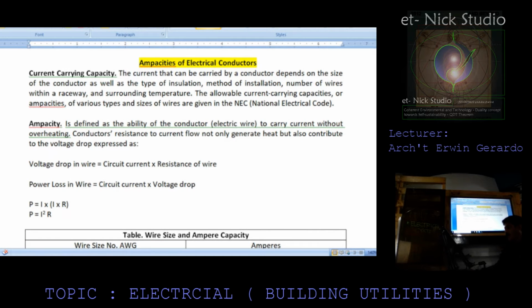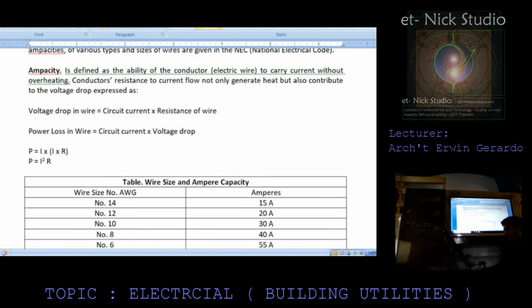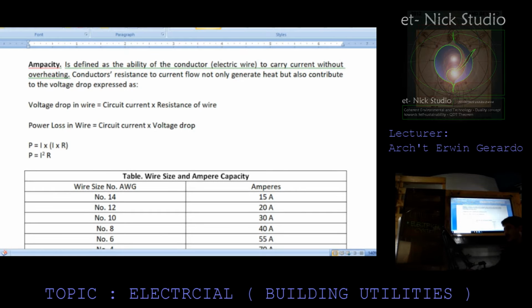Ampacities of electrical conductors. Current carrying capacity. The current that can be carried by a conductor depends on the size of the conductor as well as the type of insulation, method of installation, number of wires within a raceway, and surrounding temperature. The allowable current carrying capacities, or ampacities, of various types and sizes of wires are given in the National Electrical Code.